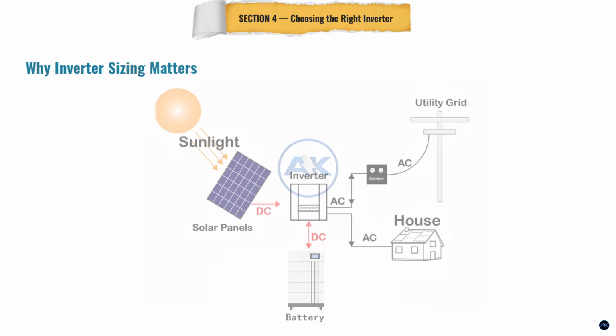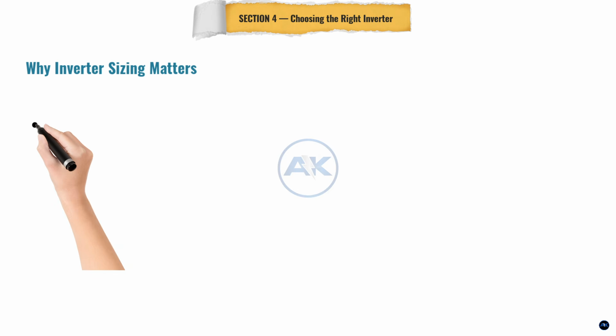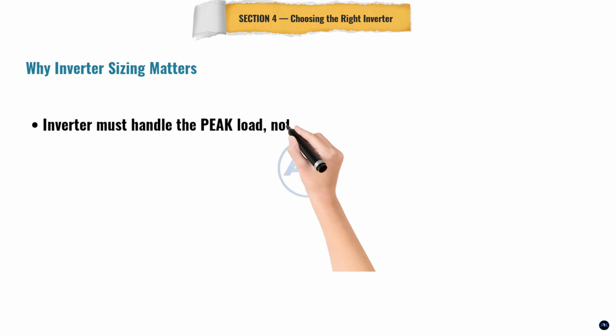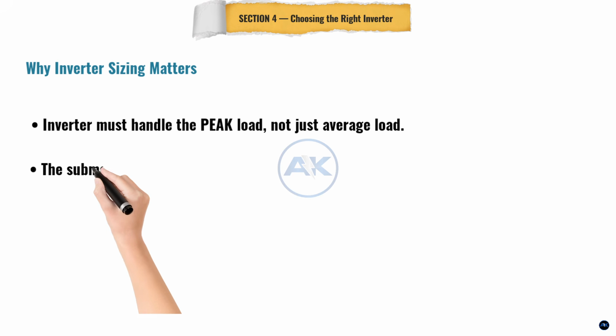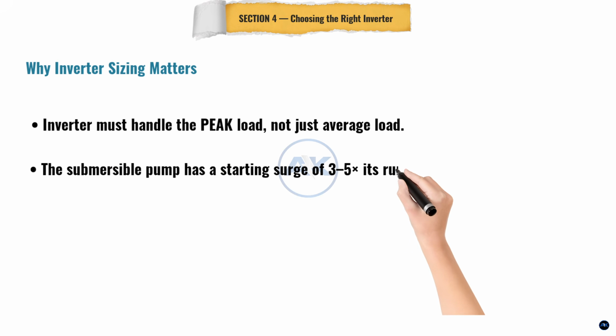Section 4. Choosing the right inverter. A hybrid inverter is the brain of the system. It manages power from the solar panels, the battery, and the grid, and delivers clean AC power to your loads. Sizing it correctly is critical, and the number one mistake people make? They look at running watts only and forget about the pump.